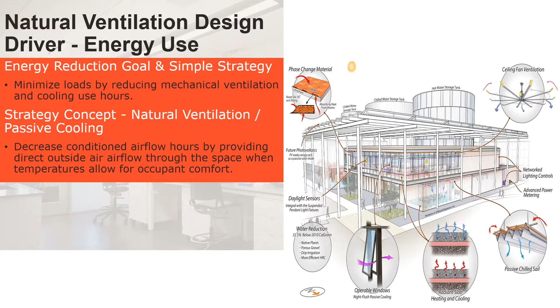This really allows each individual room to control its own temperature without impacting the room next door. When you have an air handler that serves multiple rooms, like our terminal unit above you, if you're lucky you have one per room, but that's not always the case—you might be grouped with other perimeter rooms, hopefully not mixed with interior rooms. One critical aspect for these systems is the envelope. If someone from the design team were here, they'd say it becomes so critical to make sure thermal loading from the exterior isn't impacting the building, whether at peak summer or peak winter, because your radiant floor heating and cooling combined with an open air path to the interior will create challenges. The better your envelope performs, the better these systems will perform.